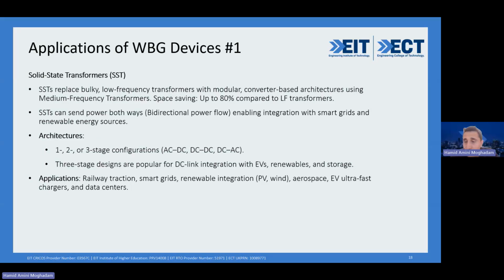Because we would like to make smaller devices, we have SST, solid state transformer. Basically we want to replace the low frequency transformer with a modular converter based architecture using a medium frequency transformer. Remember, low frequency has a bigger core cross section. If I increase the frequency, I can shrink the size of the transformer. That's the goal.